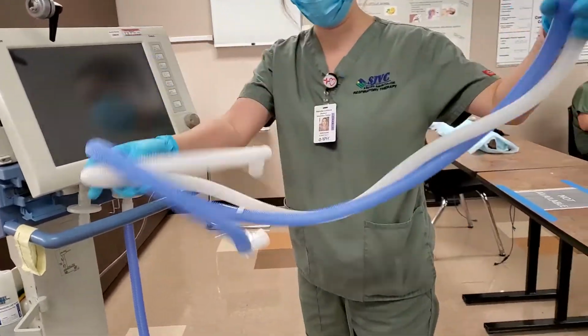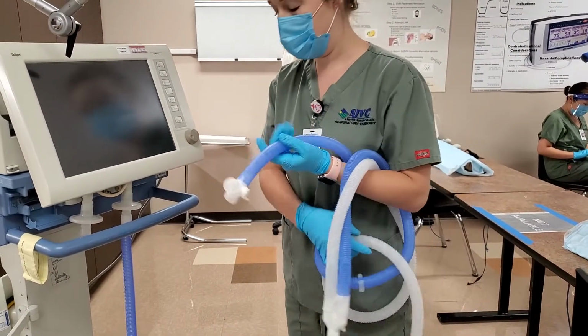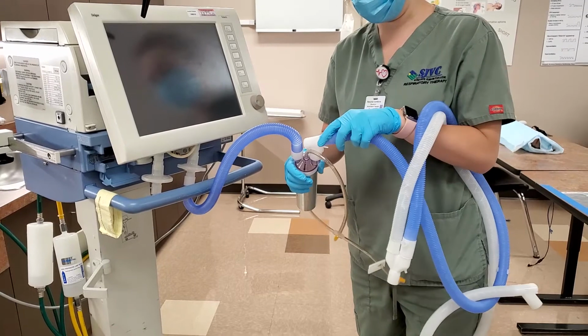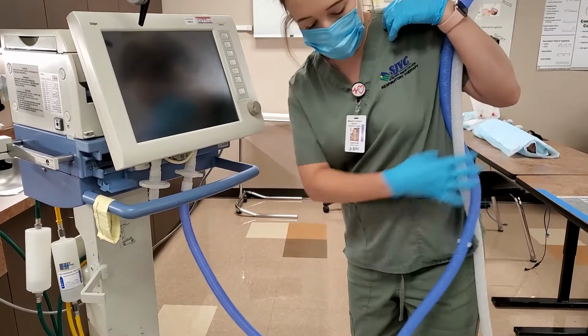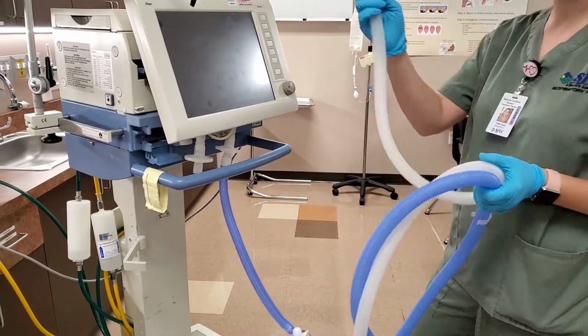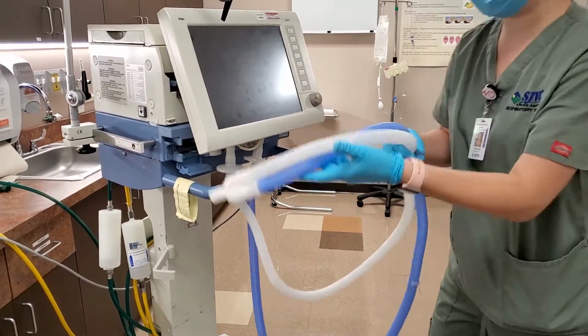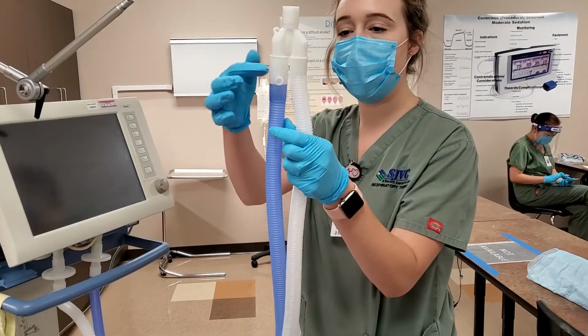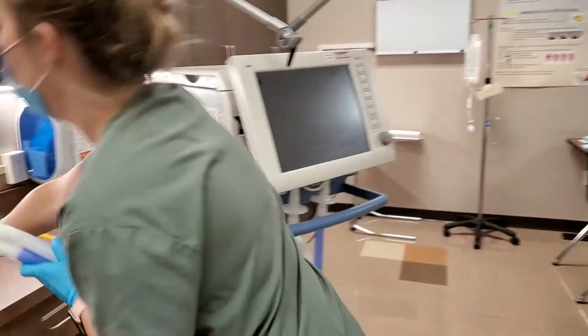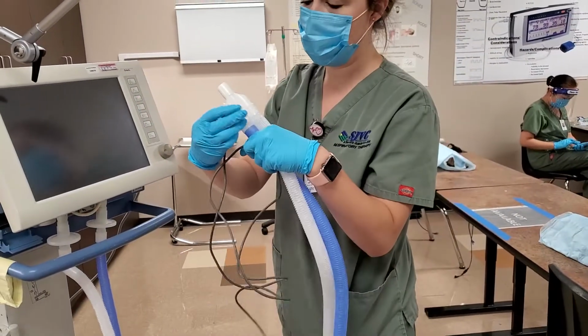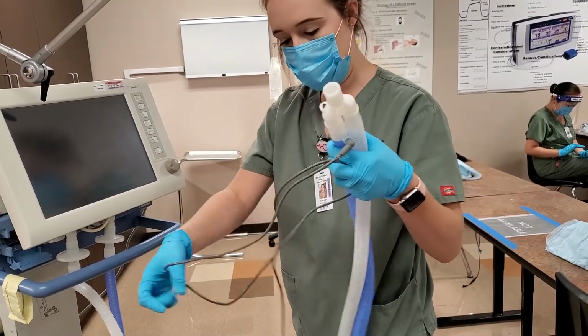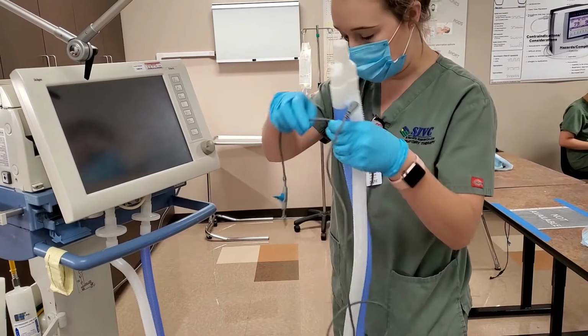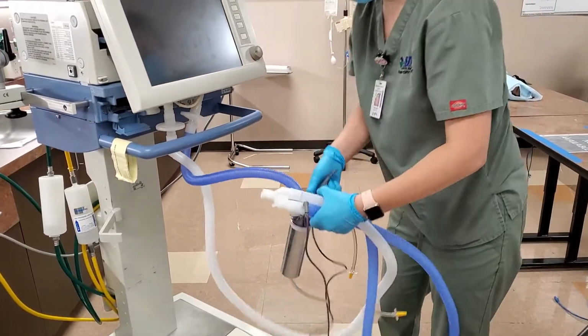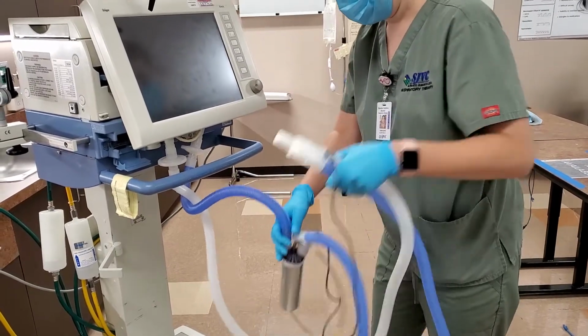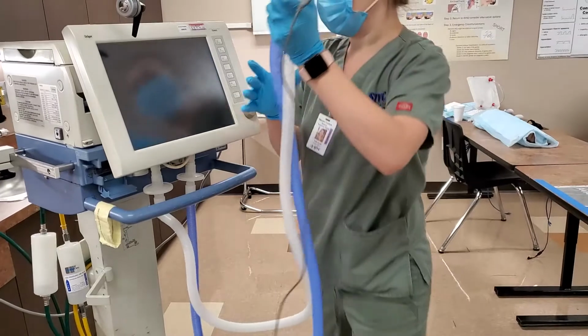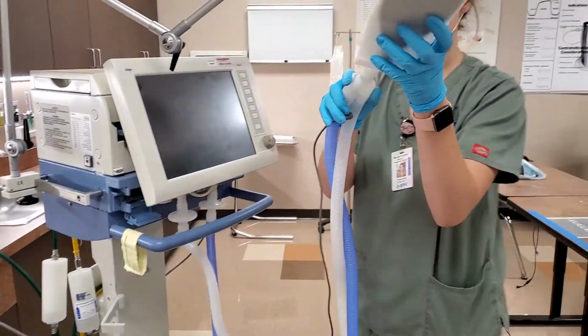You don't want to let your circuit touch the ground. Then you plug the other end of your inspiratory tube to that. And then this is your expiratory side. The way you can tell which side is the inspiratory side is that it has these ports on it, and that's for your heater wire to test the temperature, to make sure it's not too hot or too cold. So there's one port in here and another in here. And then we also have our test line here that you plug into.